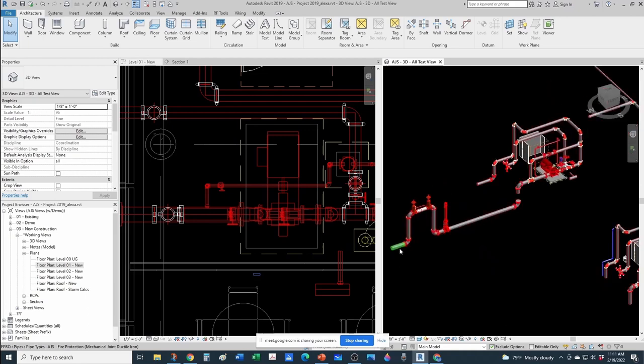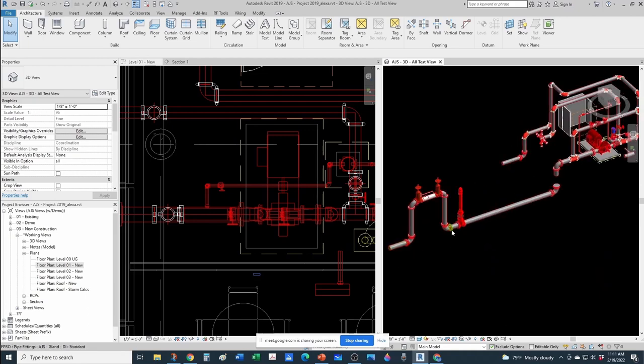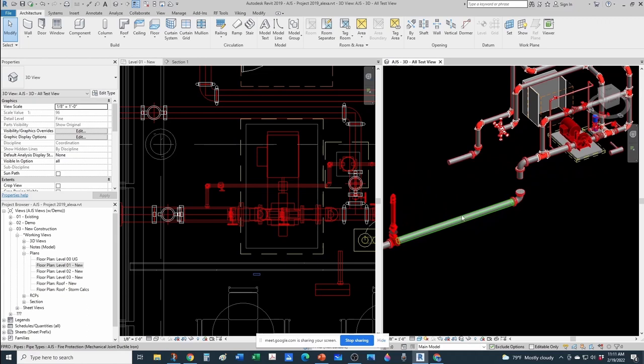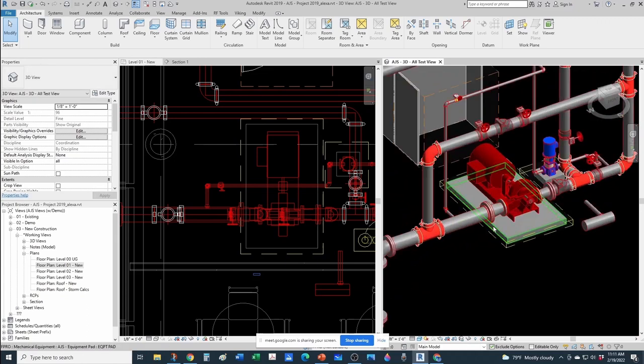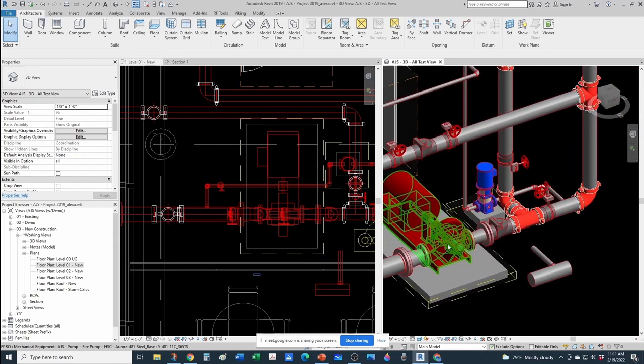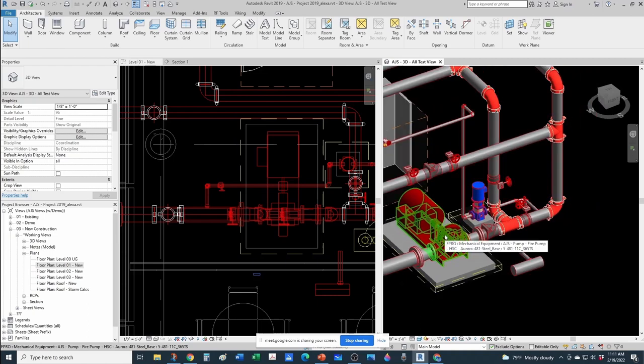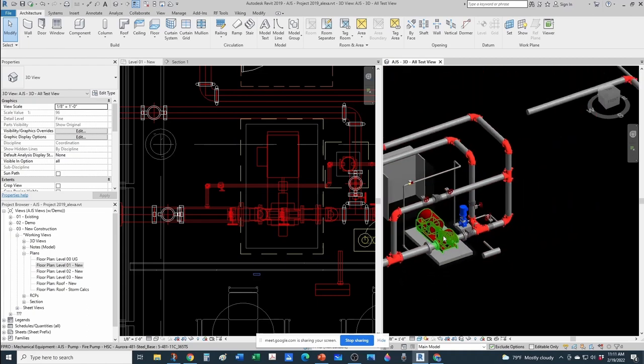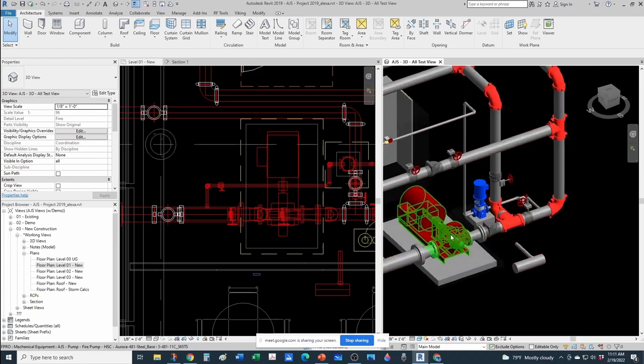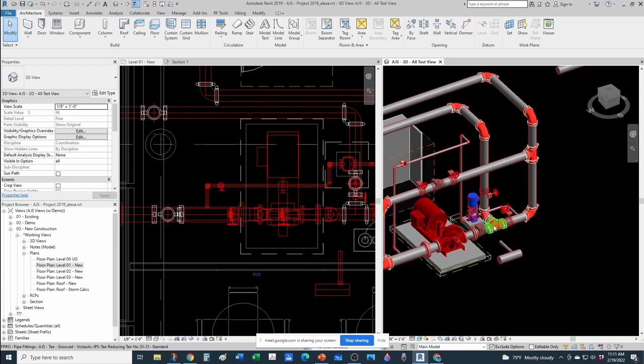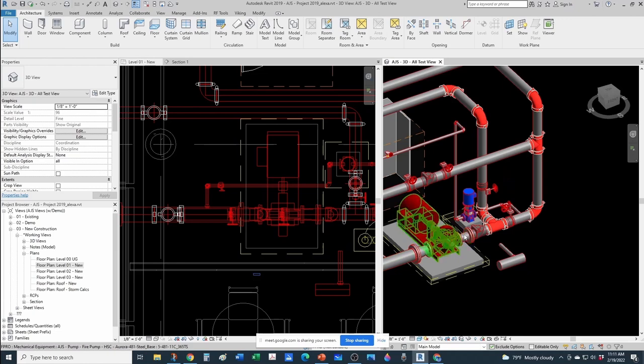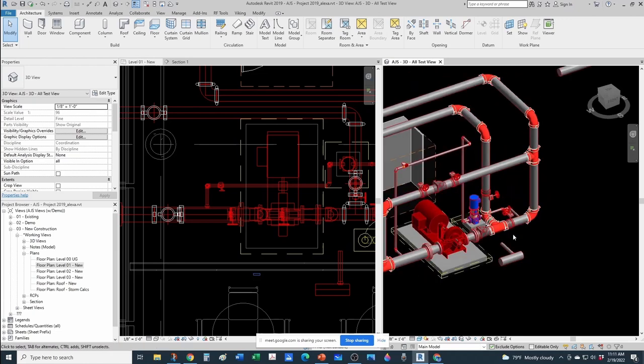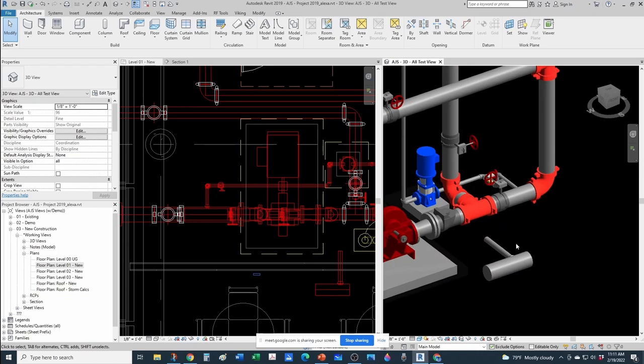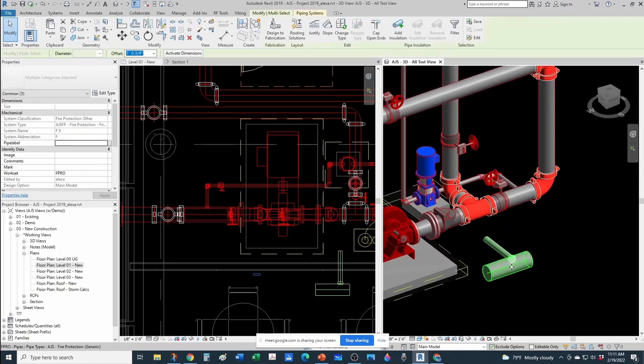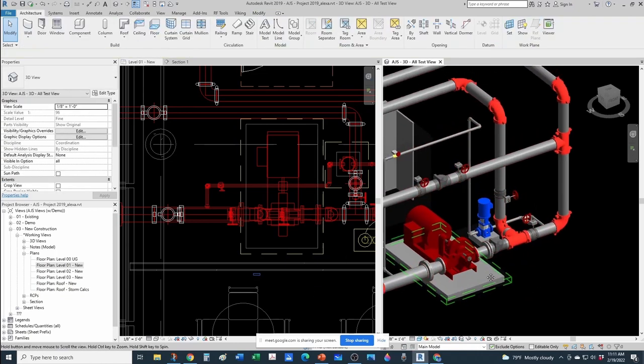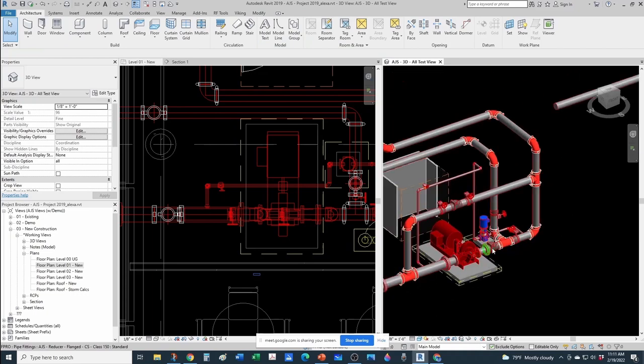So water at low pressure, let's say 40 PSI comes here, 40 or 50 PSI goes through your suction. Let's assume this fire pump is 100 PSI. So we had 40 here plus 100, 140 PSI. Obviously, we're not including the pressure drops here. It's just for explanation purposes. Hey, oh yeah, this pipe was the one that we were using as an example. So let's delete it. Then at our discharge, we have 140 PSI.